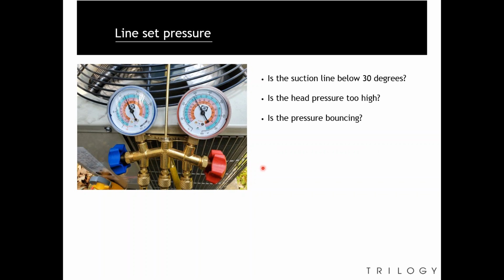Now, is the pressure bouncing? A lot of times if you see that your high side or your low side are bouncing back and forth, chances are you have a restriction on the line set, where we would need to recover the refrigerant, replace the filter dryer, pull the vacuum, and then recharge the unit.